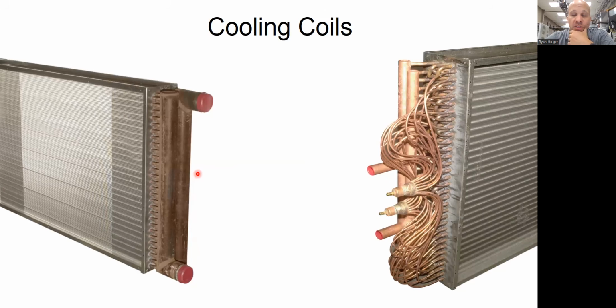So when you open the door on the air handler to the cooling coil, you will either see two headers like this, which means, let's just say, for example, chilled water comes in here at like, say, 44 degrees. It runs down this coil to the far end and goes to a U-bend, comes back, down, back, until it gets to the last row, and it fills up this return header. At that point, it's 56 degrees because warm air is blowing across this coil and giving its heat to the water. So the 44-degree water ends up cooling down to 56. We send it back to the chiller.